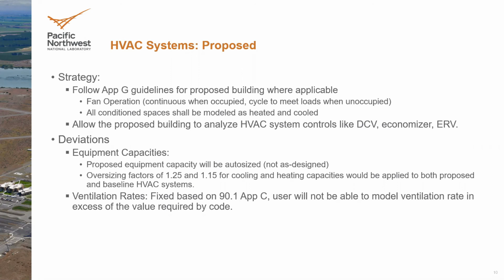It can be, yeah, where we'll need to dehumidify a little bit more. For example, take a 4-pipe chilled beam as a good example, where it's a dedicated outside air system but you're using it as your zone level heat source, and depending on the building design, how low you can dehumidify and how close to neutral air you can deliver - that'll vary based on building type and climate. 90.1 doesn't let you deliver neutral air from a DOAS system.